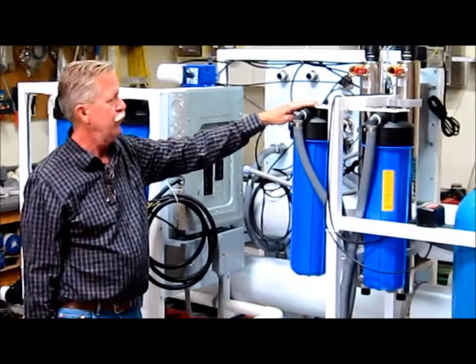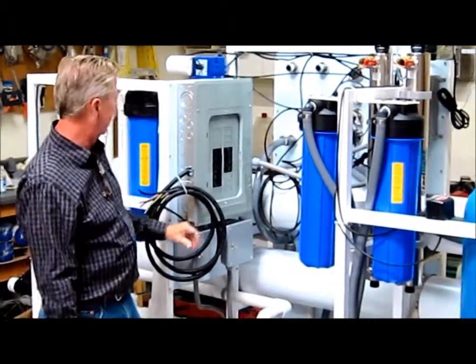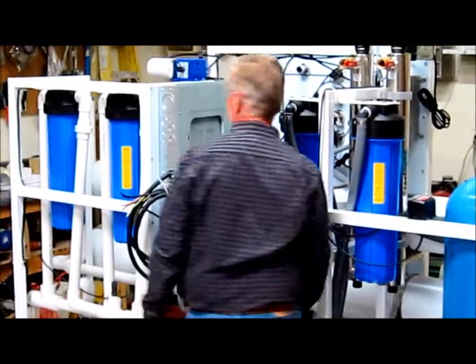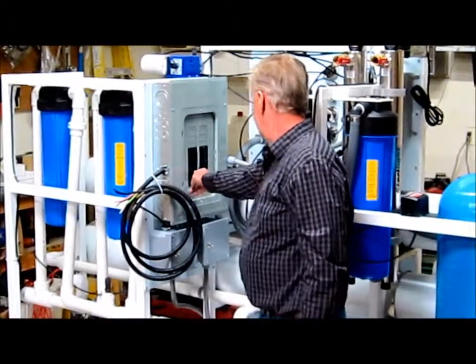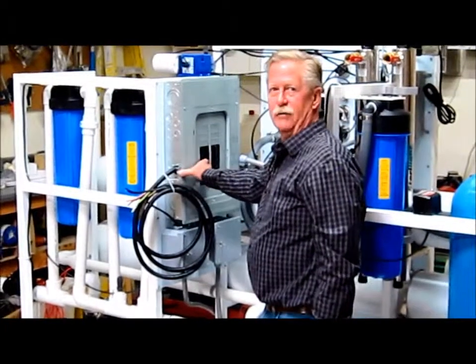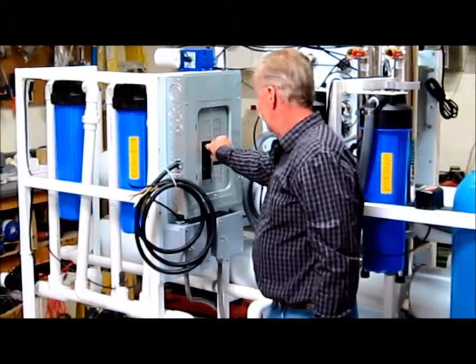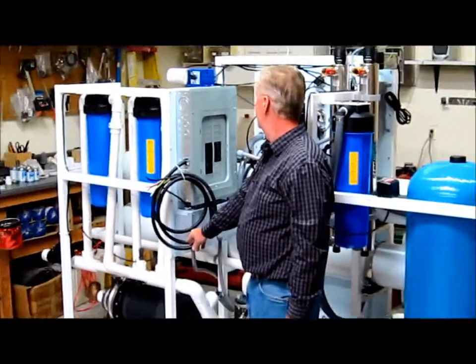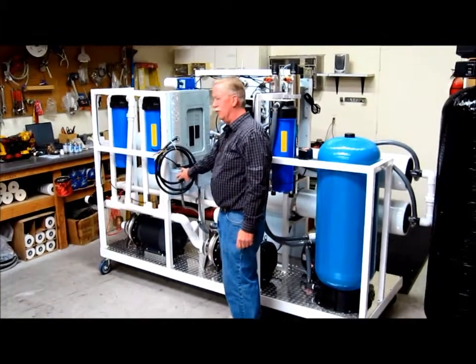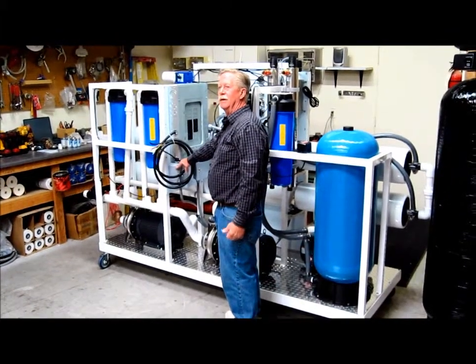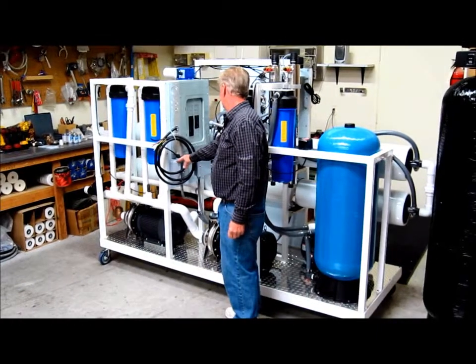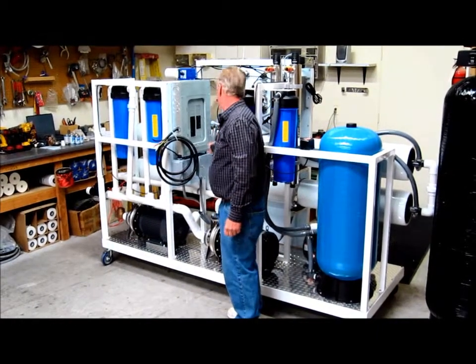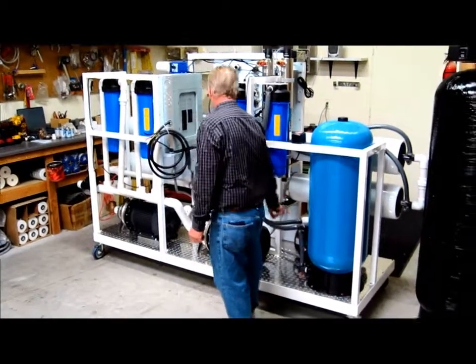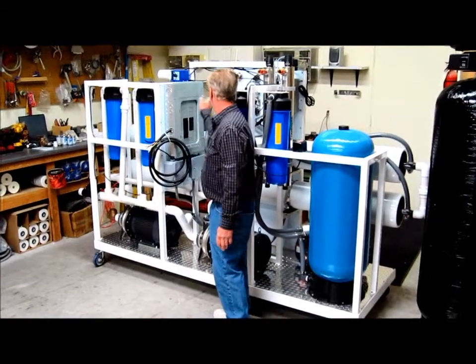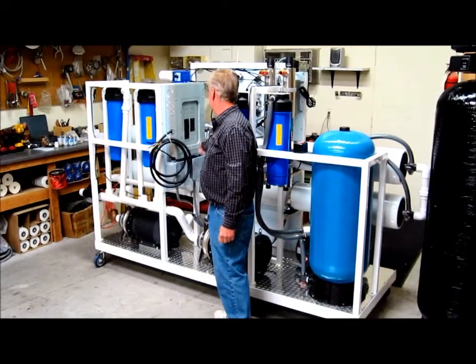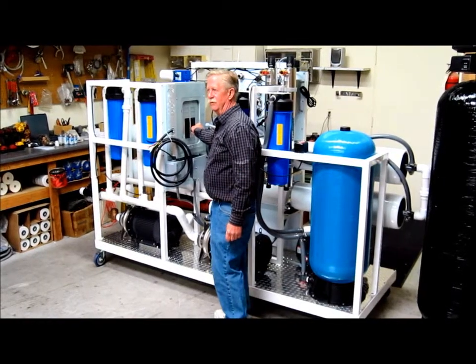Now, what we do here is this, since it's a complete system, we have an electrical panel right here with circuit breakers. So the first set of breakers would operate the feed pump, which would automatically be switched on through this box and a pressure switch to keep the pressure where it needs to be. The second box here is actually for the delivery pump, just on and off. And we got circuit breakers for running the RO part of it, and then a circuit breaker for the plugs.